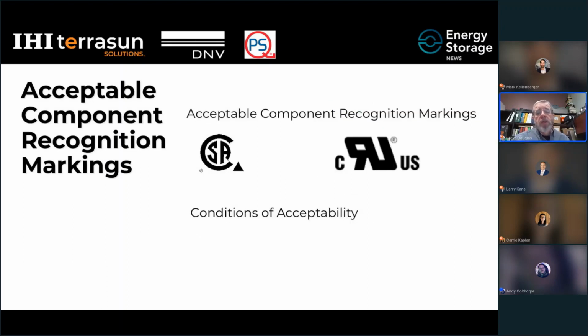The next marking you could see is a component recognition mark. There are two out there: the CSA component recognition mark, with a small triangle at the 4 o'clock position, and the UL component recognition mark, a backwards RU mark. These marks mean the product was certified, but not completely certified for use. There are usually conditions of acceptability that need to be met as part of the full certification or field evaluation for any components included that way.